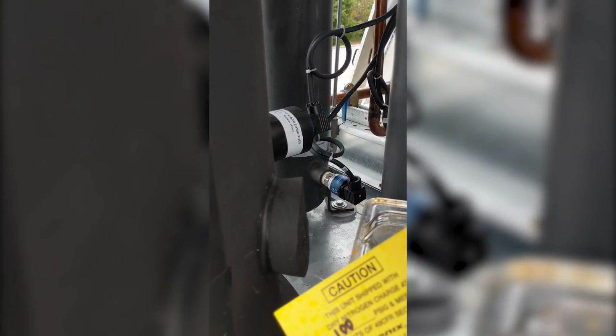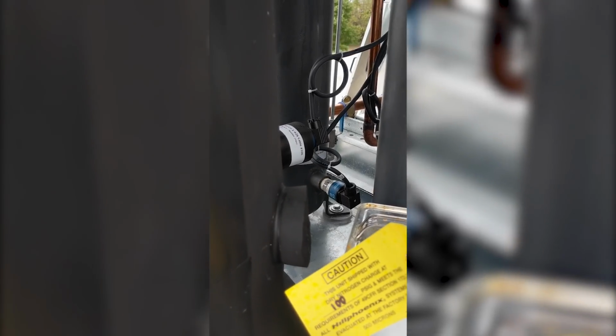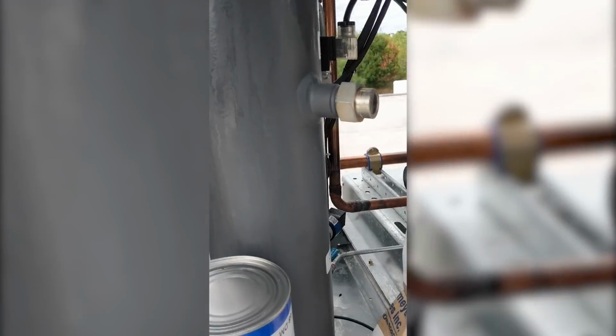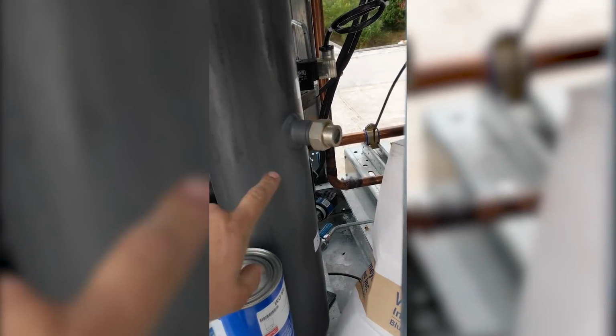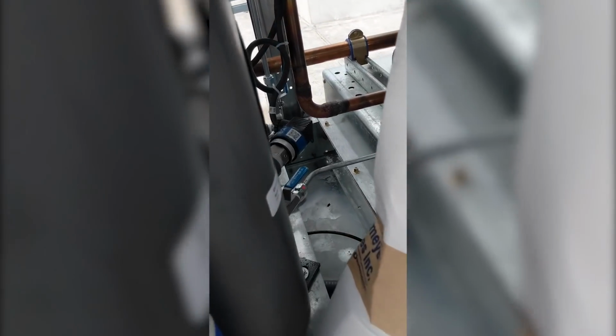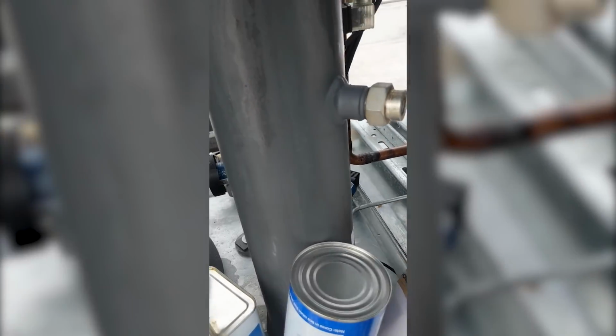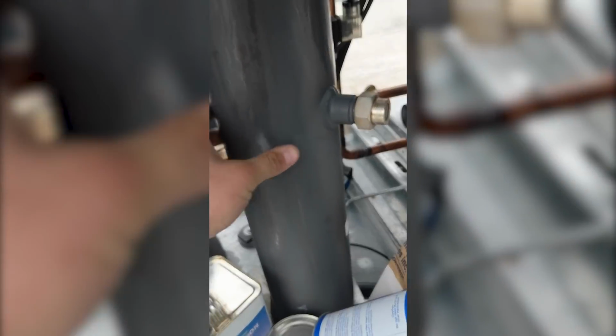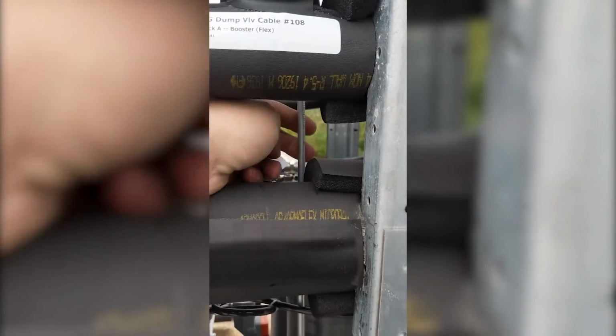Then there's this little sensor down here. When this sensor senses the oil level in the oil reservoir, it's going to open this solenoid valve right here, and it's going to pulse oil into this tank, this reservoir tank. We can maintain oil level to this sight glass, and it also has a level alarm right here. And then we're actually venting this tank off to our flash tank from this line right here. We're venting it off to our flash tank.